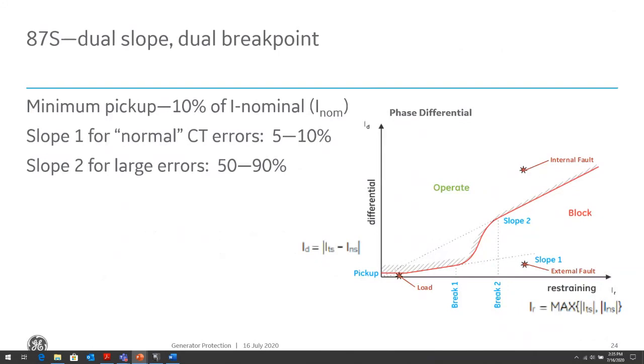And one of the ways we do that is we use the dual slope breakpoint curve, where basically there's a slope 1 and a slope 2. When we're operating in the slope 1 region, that's where we're normally operating. We're operating during normal loading conditions or within high resistive grounding faults within the zone of protection. So we expect our CT to not be susceptible to saturation within this region.